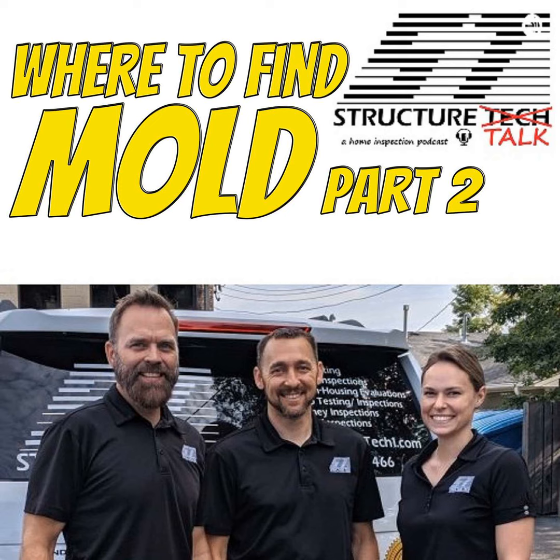I've inspected a few houses where the flex duct has some sag in it, and there's actually standing water in that. Have you guys come across that? No, in the intake? The only thing I can think of is if it's running in the summer pulling in hot, humid air, and it's in the basement where it's cool and the house is air conditioned. Well sure, what else is going to happen? Condensation, of course, and then it just sits in that duct. Since it's flex, if it's not fully supported, it'll start to sag and drip down at the lowest point. Yep, just like flex bath fan ducts in attics, that sort of thing. Yeah, so they can get real nasty.